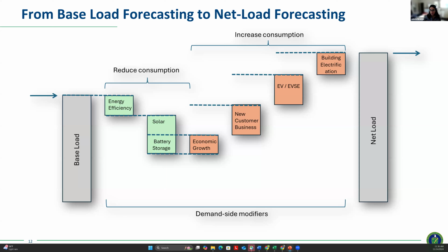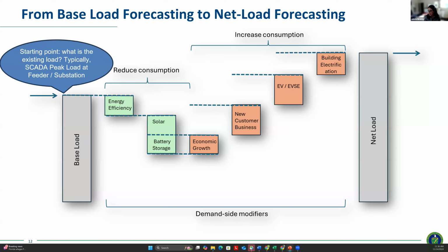So here I have how we would go from understanding the base load to the net load, with some interactive bubbles that will appear. It's important to understand what utilities are doing -- what is their starting point, how do they determine what the existing base load is. That typically comes from a SCADA measurement at the feeder head or substation. Then the local area planner might adjust that value based on economic growth and new known customer business in the area -- these are the most commonly applied methods by distribution planning utilities.